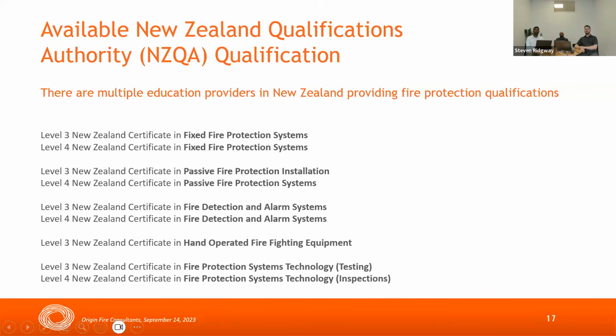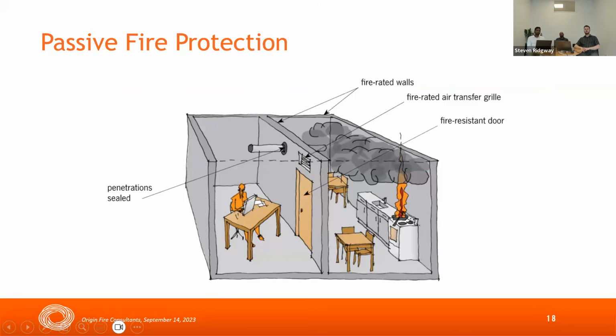Sweet. Thanks, Vinny. Next one is passive fire protection. So passive fire protection is the internal fabric of the building. It's what stops or slows the spread of fire and smoke between different compartments in a building, and we achieve this by different methods. If you look at the photograph there, there's a fire in one compartment. Let's say that's another apartment, and you don't want that fire and smoke to spread to another part of the building. So that's achieved using fire resistant separations, and then having fire stops where penetrations are made in the fire separations by various different services.